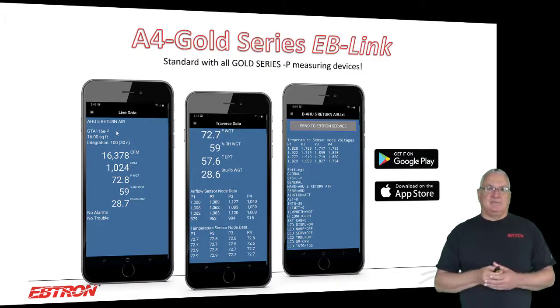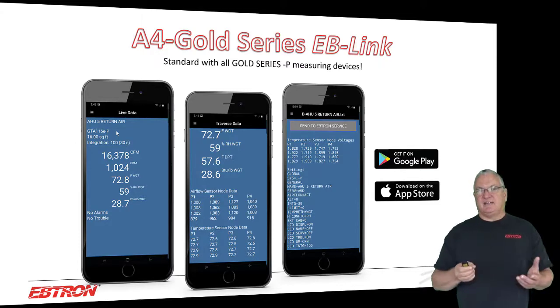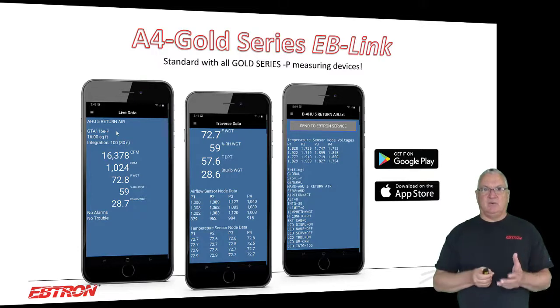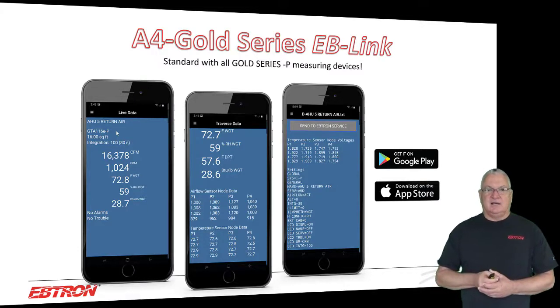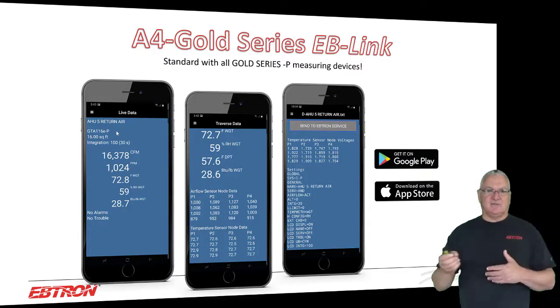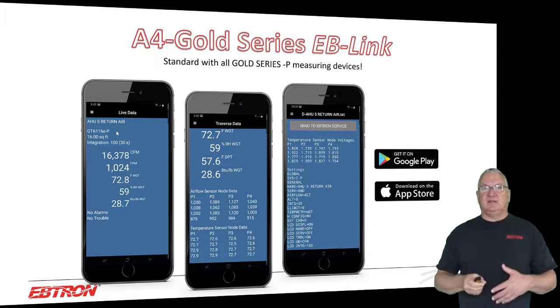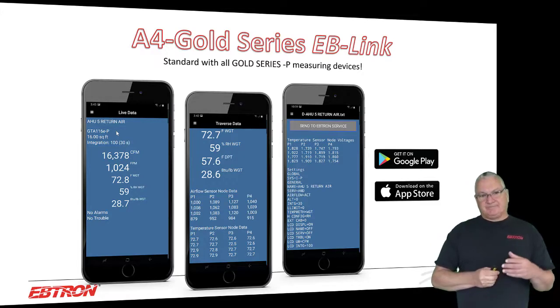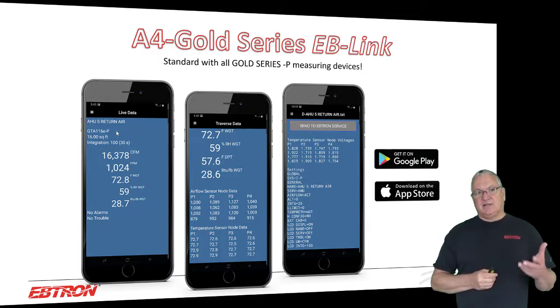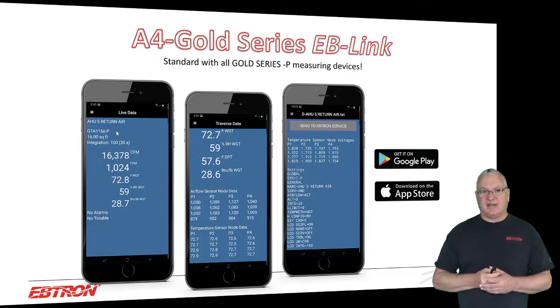When we get into the EBLink, it is fantastic. I mean, we don't charge for it, and it gives you the ability to walk into a room and see what the EBTRON is reading without going up on a ladder or wherever the transmitter enclosure is located, which means you don't have to worry about where you put the enclosure. It'll give you the airflow and the temperature, and if you had relative humidity, it'll show you that and the other psychrometric values.